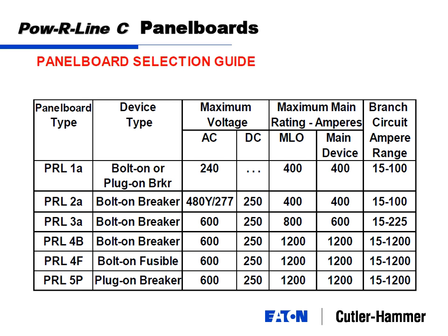Well, that's fine and great, but if you read the instructional manual in this manufacturer's literature, as well as ours, we will explicitly tell you, do not insert these panel boards hot. So now with OSHA regulations and safety and everybody following these, the whole advantage of a plug-on panel board is kind of shot, because most companies now won't let you plug things on hot in this situation. Some will, but most won't. So with that said, the 1 through 4 are the most common ones.